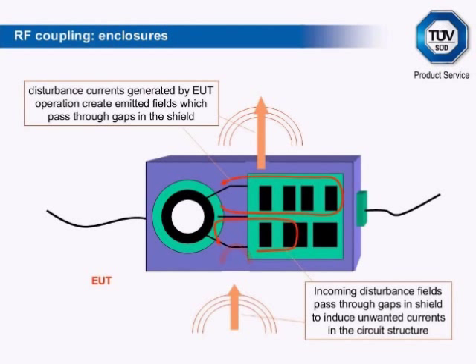The extent of the interaction is determined by the geometry and size of the conductors, with long or widely separated tracks and wires coupling greater amounts of energy into or out of the system. A shielded enclosure reduces this interaction, but no shield is perfect, and gaps or apertures in the conductive surface of the shield will allow fields to penetrate in both directions, coupling with the whole of the contents of the enclosure but particularly with structures close to the gap.